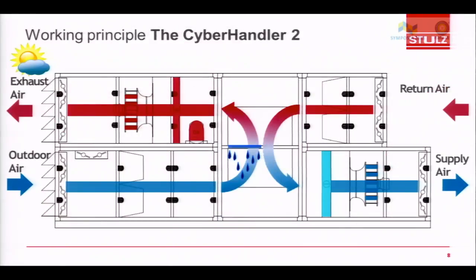Here the data center is on this side. I feel that ISHRAE is going towards data centers only, and this supplier is going to data centers. So this is data center adiabatic cooling. You have a mixing chamber available for outdoor air. We all are saying India's air is bad. Stulz has already got a solution of chemical filtration, which can be built into the filtration, and you can ensure that good air comes.